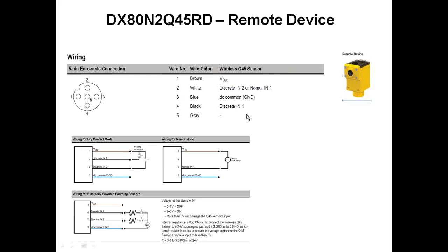The RD unit that I brought up is really handy in that what it basically is here is a node with 2 discrete inputs, and there's a connector here where you can have a field wireable or one of our QD cables, and then when you come off the end of the cable, you basically have discrete input 1, discrete input 2 feeding into this guy.